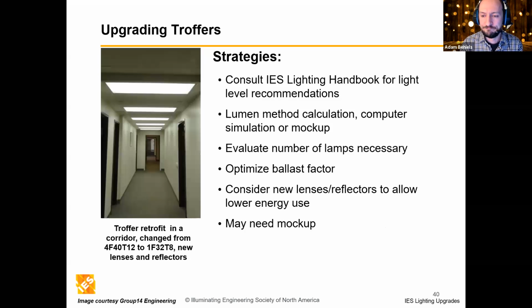Moving over to Ben - when we're looking at upgrading troffers, really this is your standard kind of T-bar 2x4 or 1x4 office setup, where you're looking at: do you want to replace the lamps in the existing fixtures, or do you want to replace with new? You're going to look at what's the better option for the client. Are these fixtures being maintained recently? Are the ballasts good? Then you could maybe just go with a lamp swap like Adam was talking about. Are the fixtures spaced correctly, or could you just go straight with a completely new redesign and layout, placing the fixtures in a new pattern that makes more sense with the LED light output?